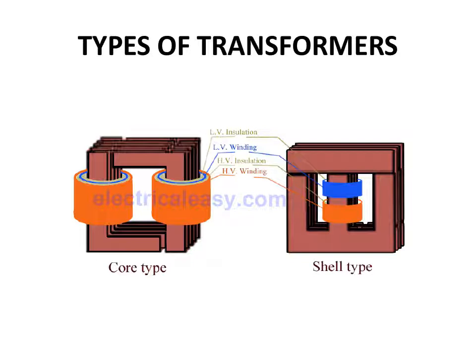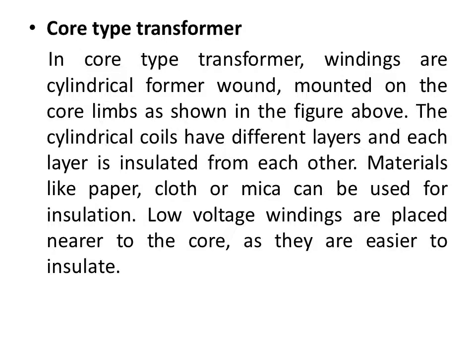In the core type, the windings are cylindrical formers mounted on the core limbs. The cylindrical coils have multiple layers and each layer is insulated from the others using materials like paper and cloth. In the core type construction, the flux has a single path — the flux flows in the core. But in the shell type, the flux has two paths, so at the center the flux is twice that of the two limbs, and the flux is divided — phi by 2 on each outer limb.